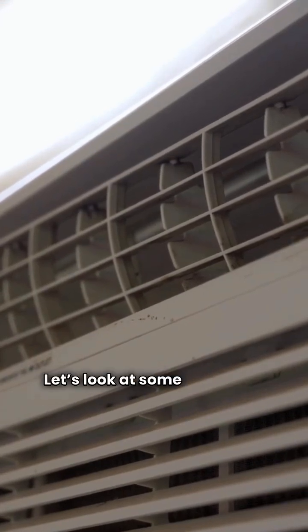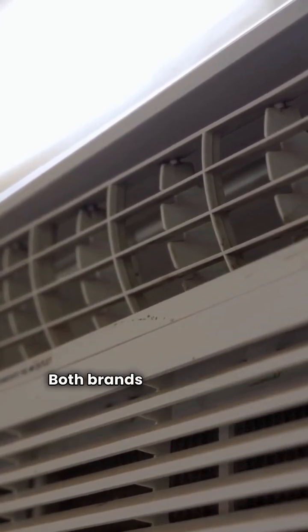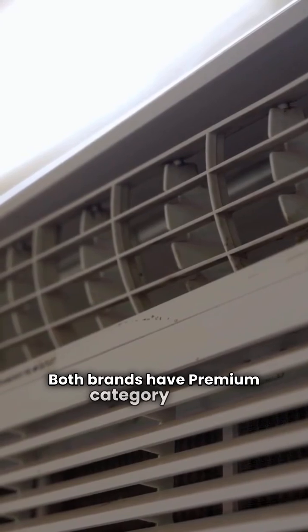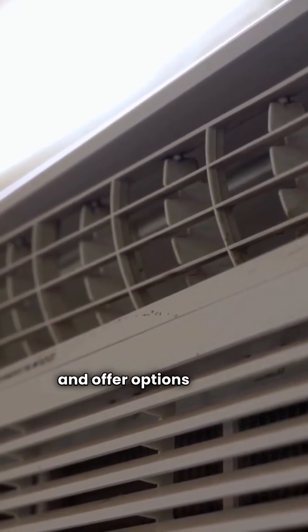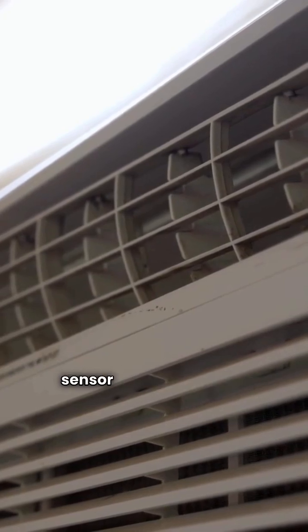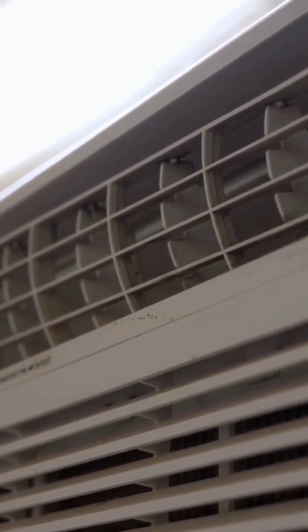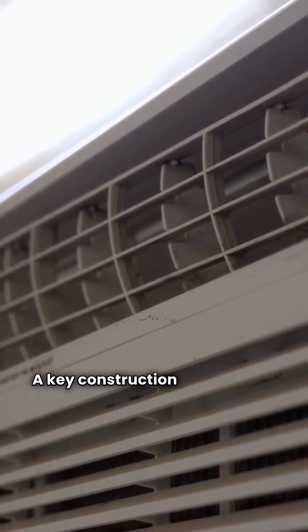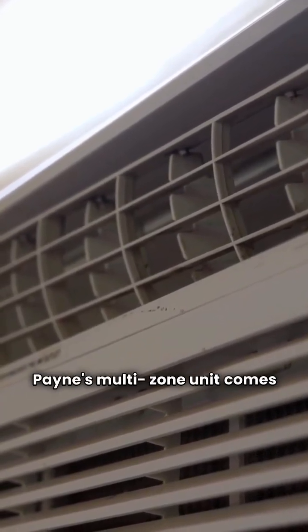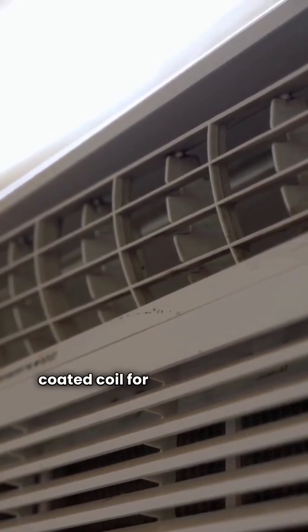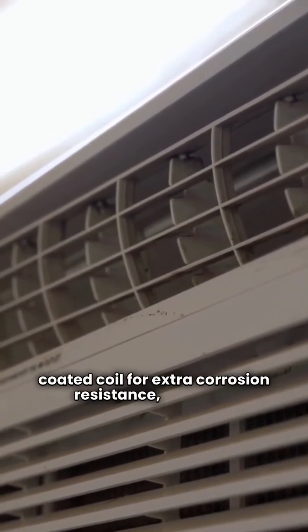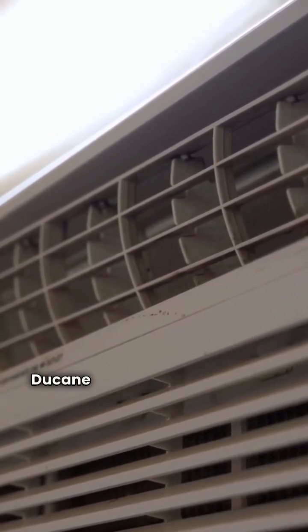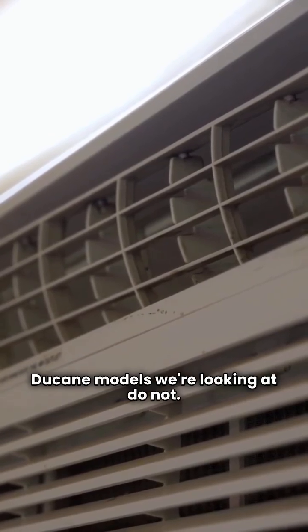Let's look at some important features. Both brands have premium category units and offer options with an occupancy sensor for better energy management. A key construction difference is the coil. Payne's multi-zone unit comes standard with a coated coil for extra corrosion resistance, while the Ducane models we're looking at do not.